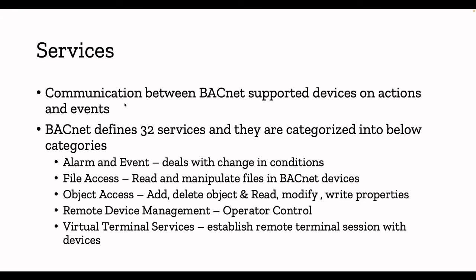The second implementation area is services, used for communication between BACnet-supported devices on actions and events. BACnet defines 32 services categorized into five categories. First is alarm and event — if something happens, say temperature goes beyond a certain threshold, it will trigger a BACnet object or device to perform some actions. That's what comes under the alarm and event category, which deals with changes in conditions. Second is file access — read and manipulate files stored in BACnet devices.